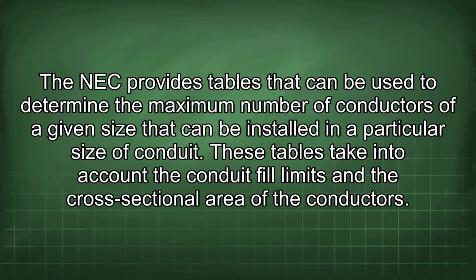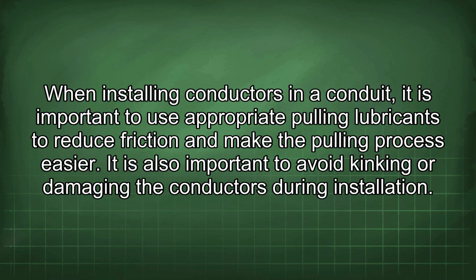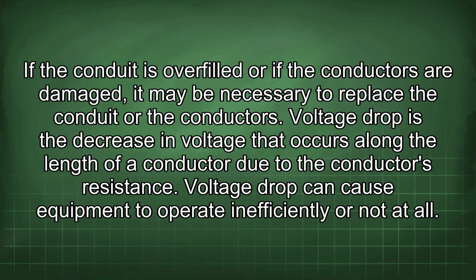The NEC provides tables that can be used to determine the maximum number of conductors of a given size that can be installed in a particular size of conduit. These tables take into account the conduit fill limits and the cross-sectional area of the conductors. When installing conductors in a conduit, it is important to use appropriate pulling lubricants to reduce friction and make the pulling process easier. It is also important to avoid kinking or damaging the conductors during installation.